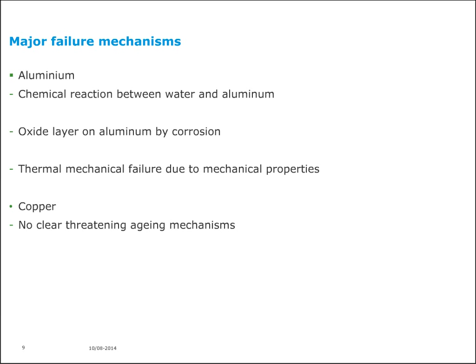Now looking to copper, we were not able to find a real or a clear threatening aging mechanism. Of course, copper is aging, but it's not resulting into serious effects resulting into failures. Well, these slides I showed you so far give an impression of the differences in material properties and also in the advantages and disadvantages of copper versus aluminum in conductors of cables. And as you could see, the advantages for copper are quite obvious.